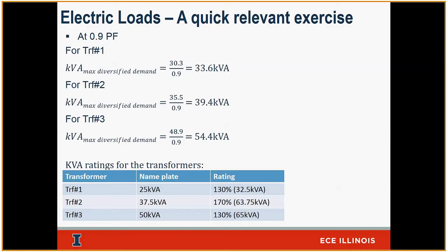So one of the very fundamental analyses that our engineers do is try to better understand how the transformer is holding up in terms of demand. Is it overloaded? Is it underloaded, right? What is the life expectancy of the transformer? Is it deteriorating? So we figure out if we need to replace it. Is it going to cause voltage problems to my customers, right? What is really going on with a transformer is one of the very basic studies that our engineers do.